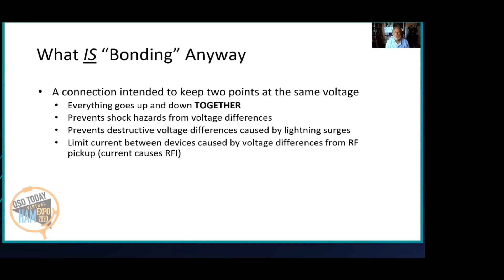But for it to work, it has to be low impedance. That means low ohms, either reactance or resistance, and it has to be electrically short at the frequencies of interest. Down at AC, where the wavelength's about 5 million meters, that's not so hard. But up at 10 meters, for example, well, the wavelength's a lot shorter. Anything over about a 20th of a wavelength is going to start acting like a transmission line, not so much a grounding wire. So you want to make sure everything stays as short as possible at the frequencies you're trying to manage for bonding to actually work and keep everything at the same voltage. It has to be heavy enough to carry the expected current. This is true at AC safety, where you're trying to carry fault currents that are heavy enough to trip a breaker. It's also very true in lightning protection, where you may be trying to handle hundreds or thousands of amps for a short period.